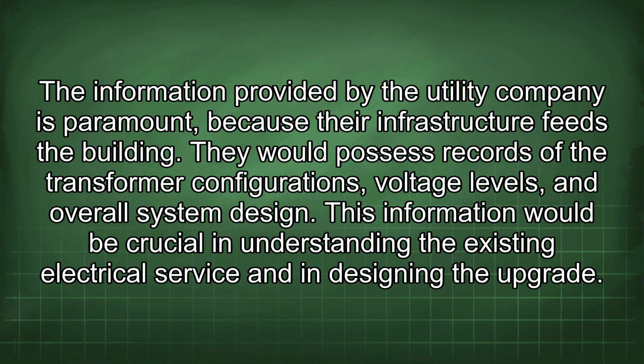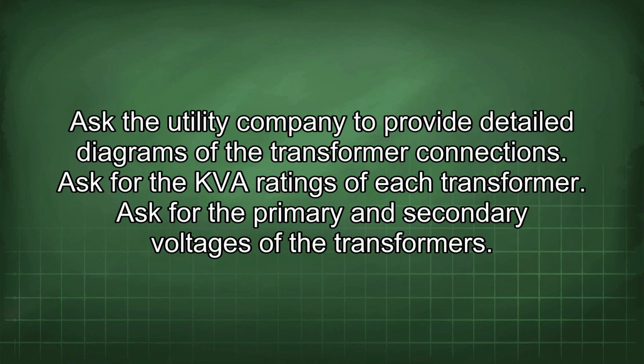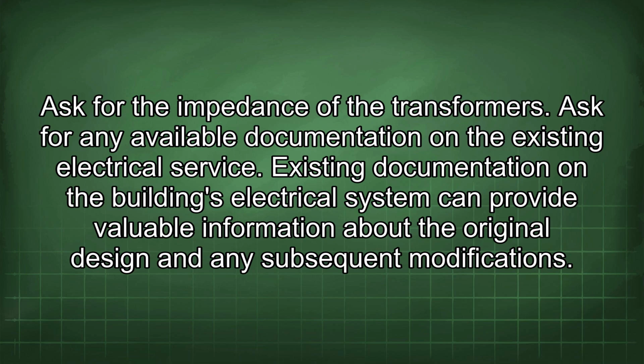The information provided by the utility company is paramount because their infrastructure feeds the building. They would possess records of the transformer configurations, voltage levels, and overall system design. This information would be crucial in understanding the existing electrical service and in designing the upgrade. Ask the utility company to provide detailed diagrams of the transformer connections. Ask for the kVA ratings of each transformer. Ask for the primary and secondary voltages of the transformers. Ask for the impedance of the transformers. Ask for any available documentation on the existing electrical service.